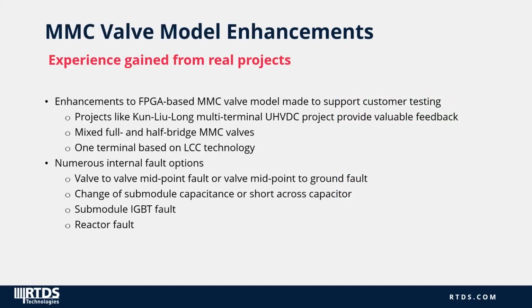We have made a number of enhancements to our FPGA-based MMC valve models, some of which came from practical experience gained through projects like the Kun Liu Long multi-terminal UHVDC project in China. The Kun Liu Long project was particularly interesting. A couple of highlights are that it is a multi-terminal project with 2 MMC-based terminals and 1 LCC-based terminal. Another interesting feature is that the MMC valves are a mixture of both full and half-bridge submodules.